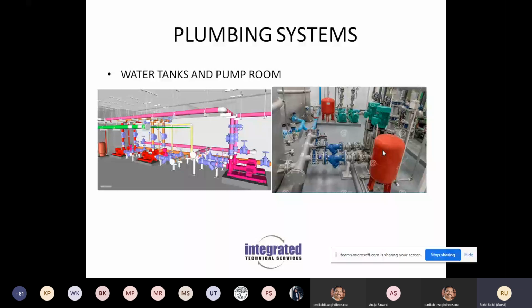Now, a hydropneumatic system again works automatically. If there are 100 taps that the system is supplying to, once 3 taps or 4 taps or 10 taps are opened, the pressure in the system allows the water to flow out, and the moment the pump senses that the pressure in the line is going down, it starts automatically, and once the pressure is achieved again, it stops. Hydropneumatic systems are used quite extensively, especially in hotel projects and in commercial projects or in buildings where, because of height restrictions, we are not able to provide overhead tanks. And so the lines run at the ceiling of the basement and directly enter into the shaft and supply to the various outlet points.